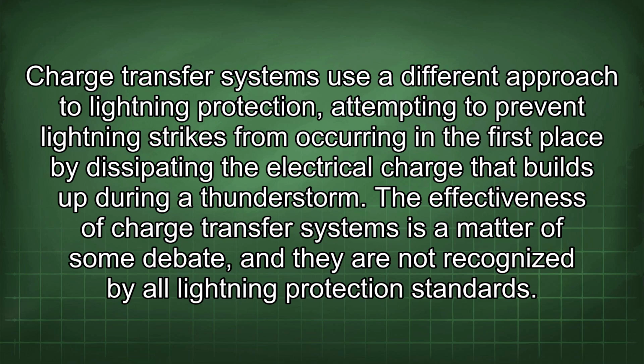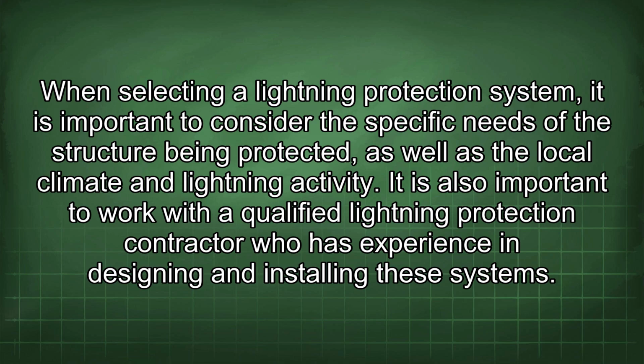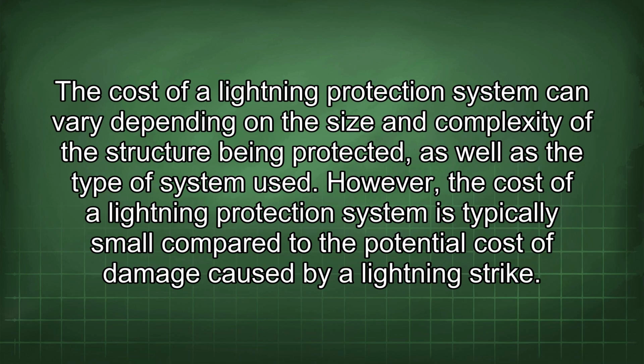The effectiveness of charge transfer systems is a matter of some debate, and they are not recognized by all lightning protection standards. When selecting a lightning protection system, it is important to consider the specific needs of the structure being protected, as well as the local climate and lightning activity. It is also important to work with a qualified lightning protection contractor who has experience in designing and installing these systems. The cost of a lightning protection system can vary depending on the size and complexity of the structure being protected, as well as the type of system used. However, the cost of a lightning protection system is typically small compared to the potential cost of damage caused by a lightning strike.